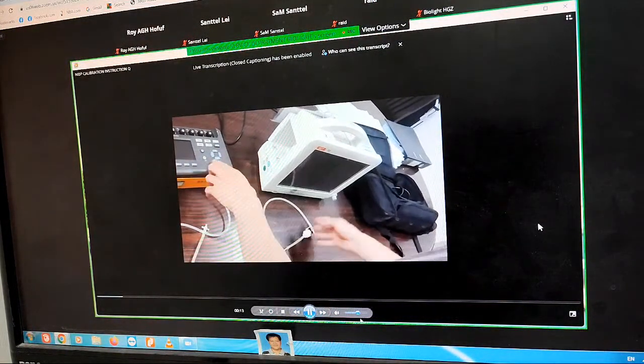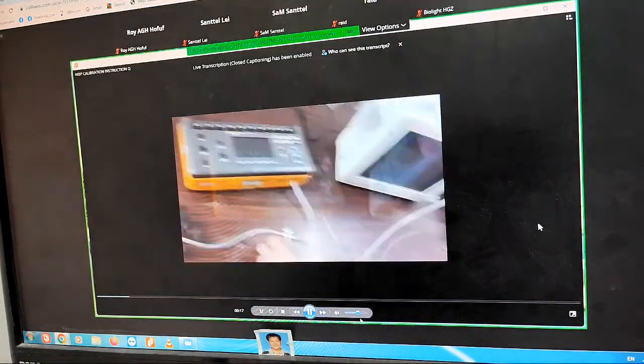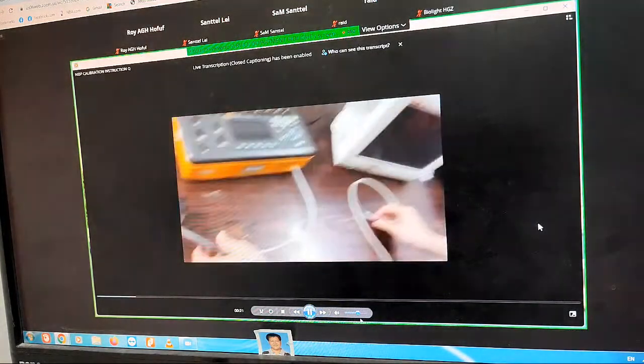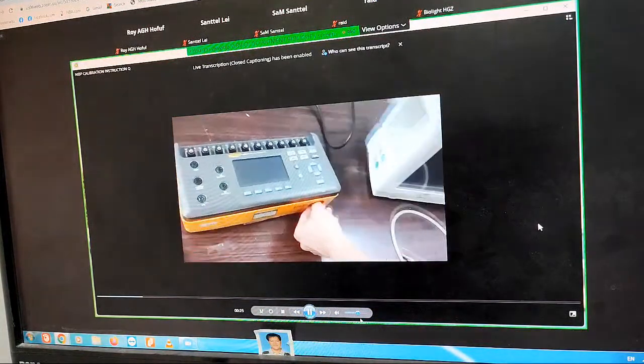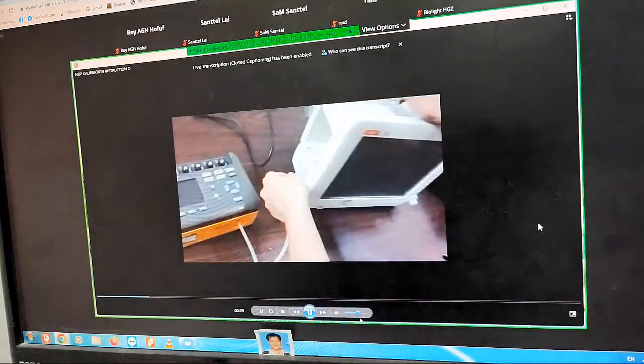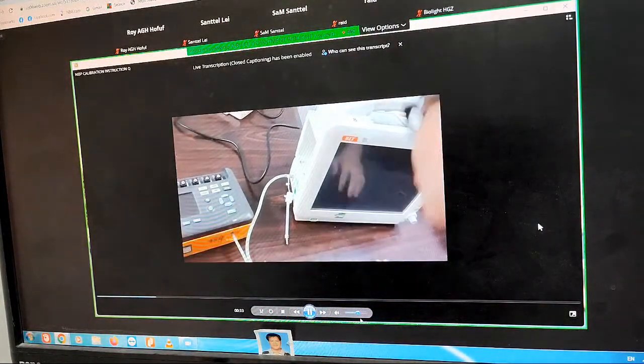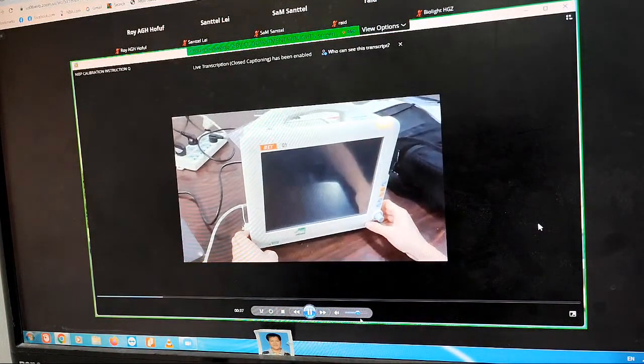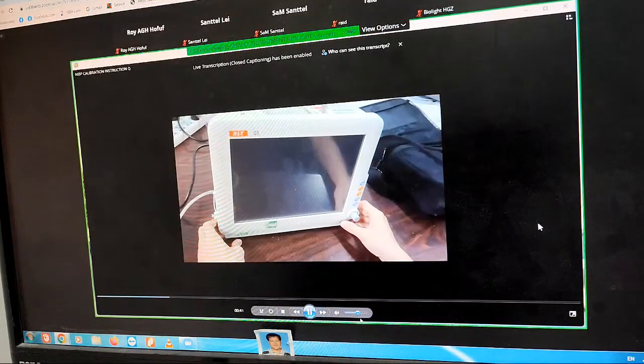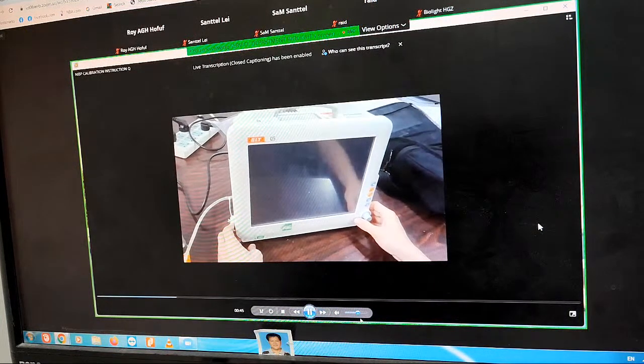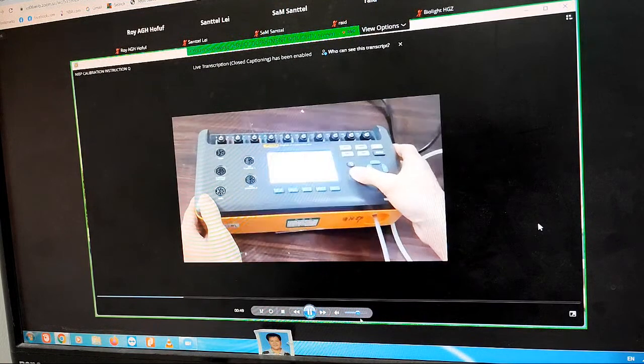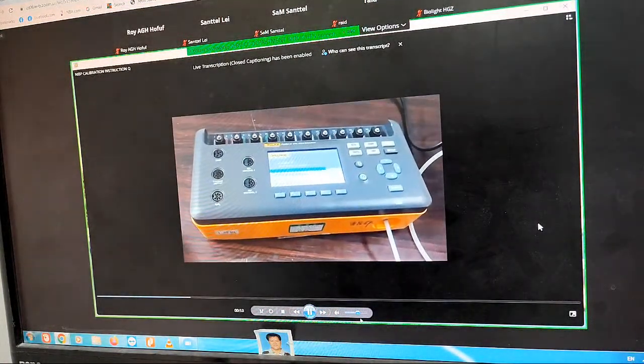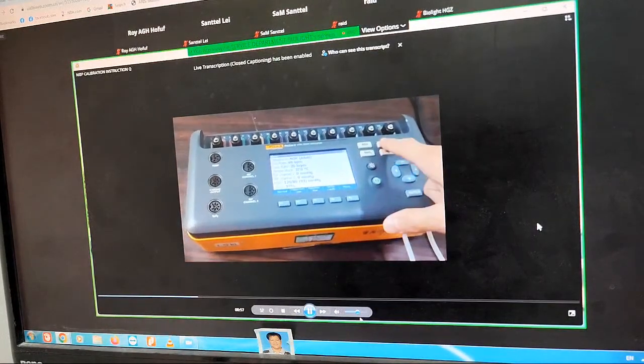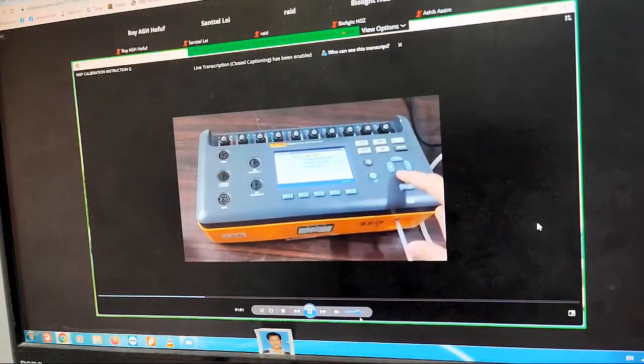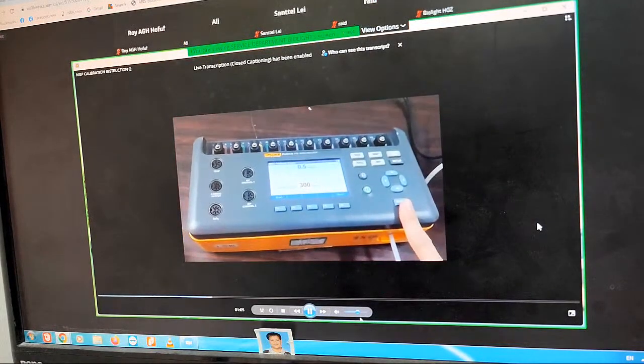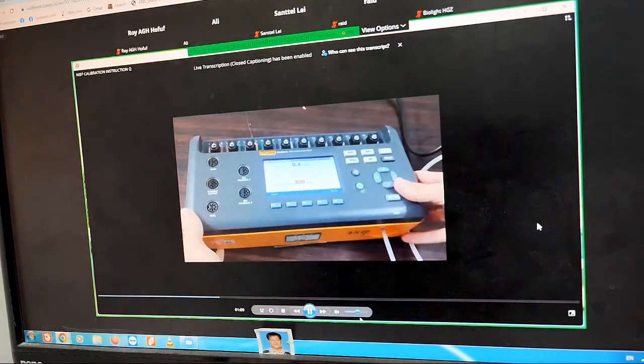Now we're going to calibrate the NIBP for the patient monitor. First, we should have the three-way tube: one connects to the NIBP cuff, one connects to the simulator, and one connects to the patient monitor. Now we start with the patient monitor first, then we can start the simulator and set the target pressure to 200 millimeters of mercury.